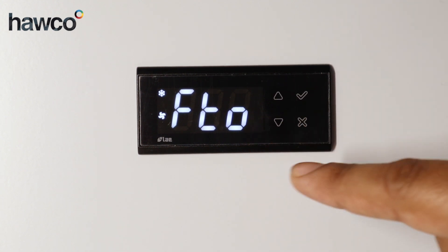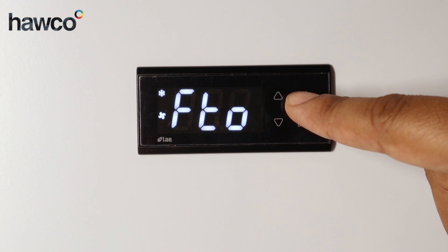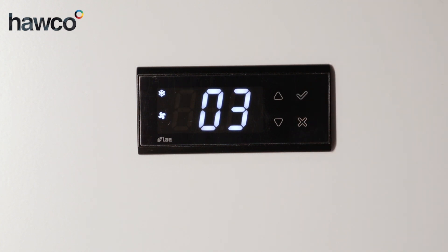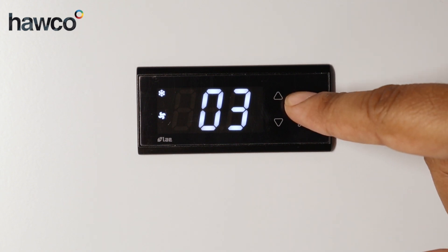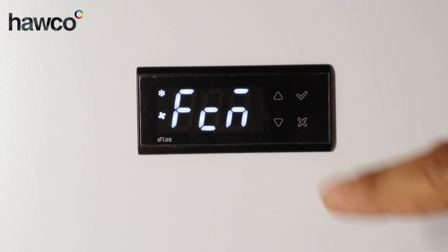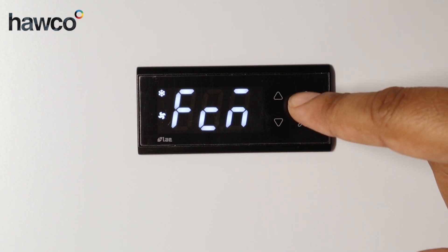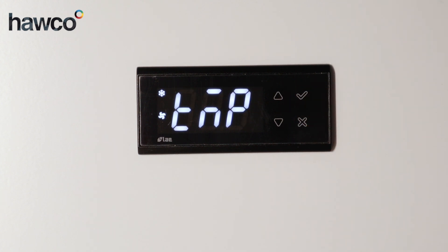The first parameter is FTO, which is the maximum effective fan stop. It's set to three minutes. The next one is FCM, which is fan mode during thermostatic control. This one is set to temperature.